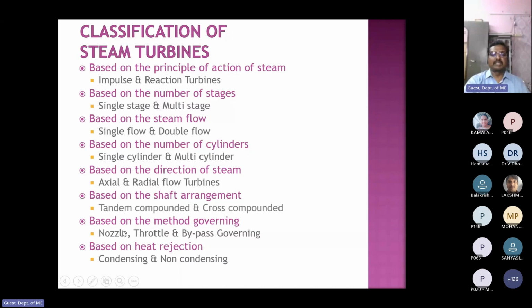There are different types of governing: nozzle governing, throttle governing, and bypass governing. When different sets of nozzles are used to control the steam input, that is called nozzle governing. Impulse turbines use nozzle governing. In the case of reaction turbines, throttle governing is used. Throttle governing is just like our bike's acceleration or reduction. Here we have a control valve that opens and closes as per the requirement.